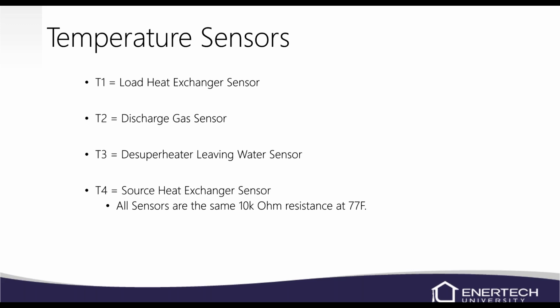And we do have a chart in the manual that'll give you some resistance readings based on temperature so that you can read that sensor and ohm it out and see what temperature it's reading. I will say we don't have a lot of problems with these sensors reading a wrong temperature. Normally they'll either be open or shorted is how they normally fail. They don't normally read a wrong temperature.